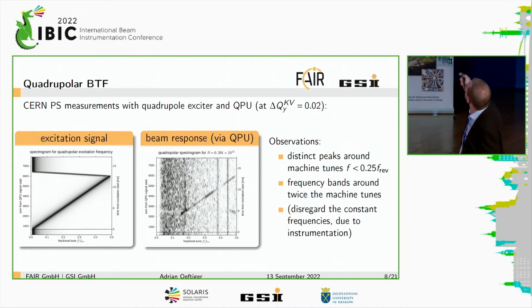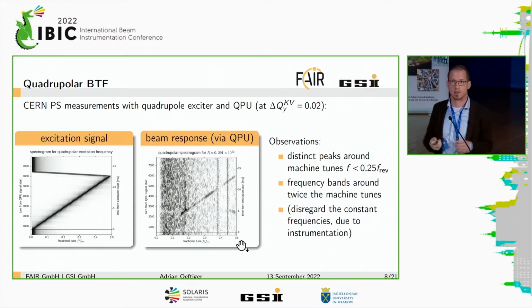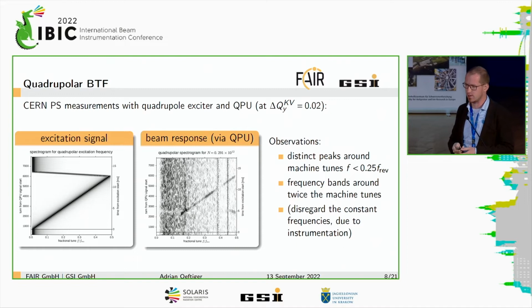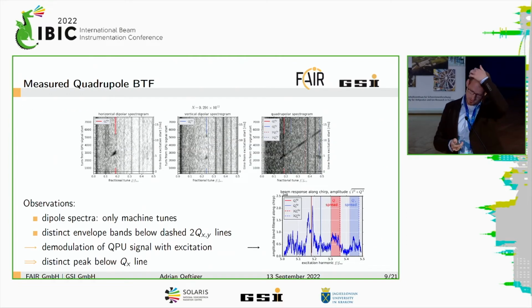And you can already see that there are a lot of lines here, and there are distinct peaks around the machine tunes that I've set to something below 0.25. And then you see frequency bands up here that are related to twice the machine tunes. That's the envelope bands we're searching for. Here it was a bit difficult at times because of these instrumentation affiliated noise lines. So therefore it's not simply an FFT that you can take, but you need to do the demodulation to see it properly. So let's have a look at the 3 different spectra taking exactly this experiment.